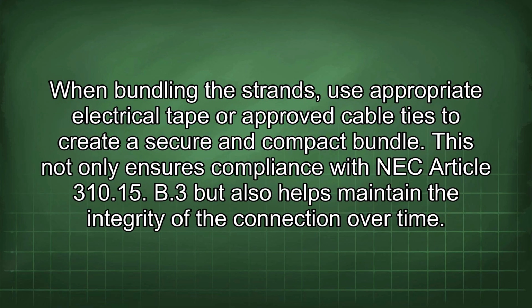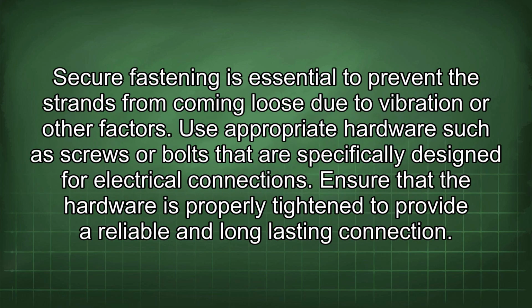When bundling the strands, use appropriate electrical tape or approved cable ties to create a secure and compact bundle. This not only ensures compliance with NEC Article 310.15 B3 but also helps maintain the integrity of the connection over time. Secure fastening is essential to prevent the strands from coming loose due to vibration or other factors. Use appropriate hardware such as screws or bolts that are specifically designed for electrical connections. Ensure that the hardware is properly tightened to provide a reliable and long-lasting connection.